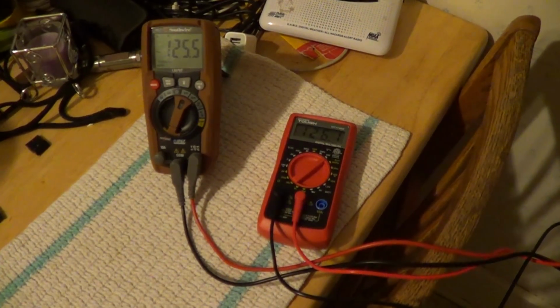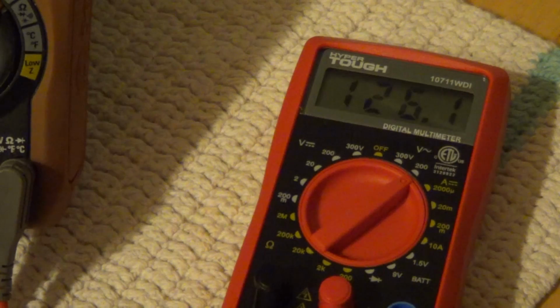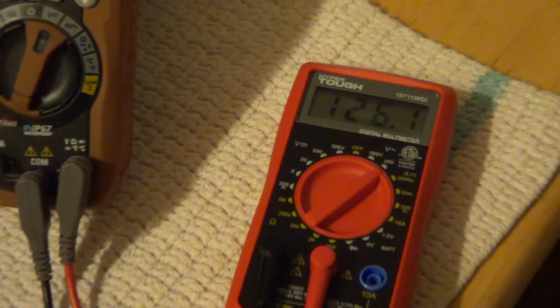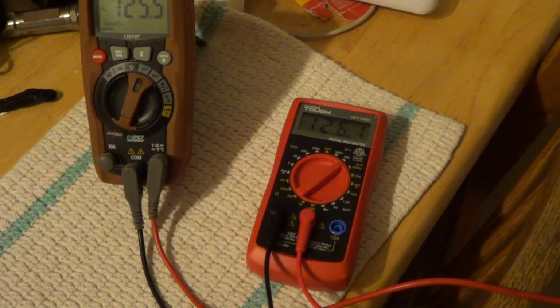If we take a closer look at the Hyper-Tough meter, you can see it's reading 126 volts AC even, my line voltage is a little high around here. By comparison, the Southwire meter, which I believe reads a bit low, is reading just half a volt lower than the Hyper-Tough. However, there's an important qualification to consider when making AC voltage measurements with a simple, inexpensive meter like this.